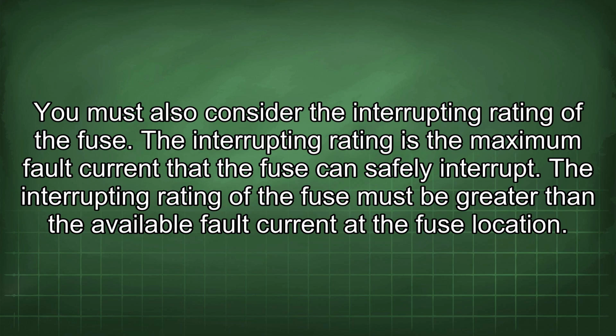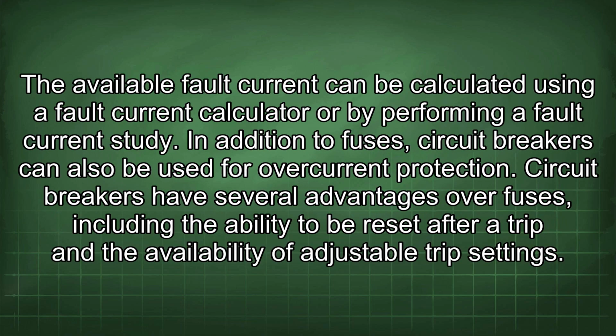The interrupting rating is the maximum fault current that the fuse can safely interrupt. The interrupting rating of the fuse must be greater than the available fault current at the fuse location. The available fault current can be calculated using a fault current calculator or by performing a fault current study.